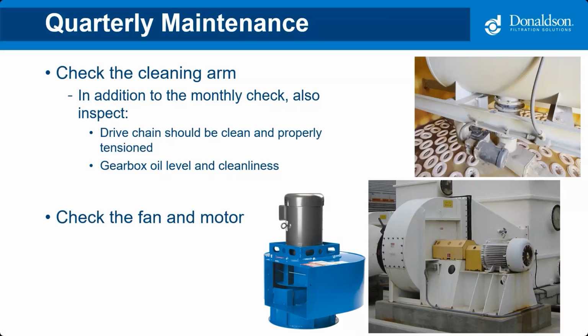And then lastly is a much deeper inspection of the fan and the motor. There's a couple of pictures there as an example. You're checking for temperature. You know, is the fan running hot? Are you hearing noise, vibration? You're doing a bearing inspection. You want to make sure they're all properly lubed, oil, grease, whatever your particular fan and motor setup is. And then any belts or drive chains that are associated with it are all properly tensioned and lubricated. So it's a much deeper inspection of that fan and motor system.